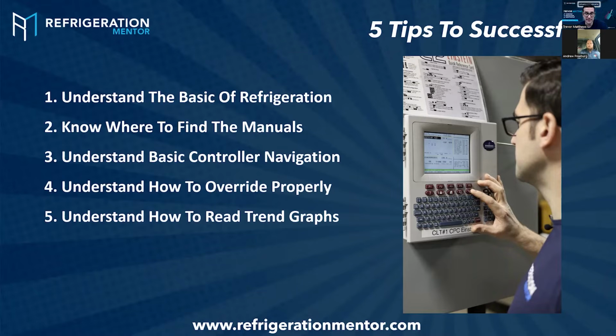But at the end of the day, I hear the exact same thing as what you just said from any controller expert. The controller information is only as good as the input information it's getting: pressure transducers, temperature probes, humidistats, whatever it's reading. The information on those graphs or on those sensors is only that good. Another thing that I've noticed too is improperly set up set points, and that's where it could cause a lot of issues. Have you ever noticed the temperature set too low, maybe defrost termination set too high, or maybe the deadband's too close? Have you ever come across any of that before, Andrew?